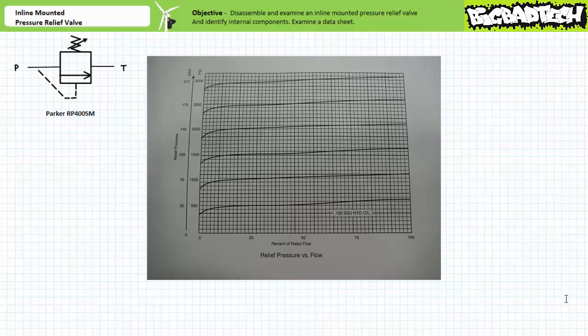The amount of diverted flow steadily increases as pressure approaches the full open value. This is to suggest that an actuator operating at regions near the set limit might show a lag in speed since an increasing portion of flow rate is being diverted through the progressively increasingly open pressure relief valve. This being said, you only experience this at regions very close to the set limit when an actuator is just about to stall out at the limits of travel anyways. Adjusting the pressure relief valve set value up or down, one would have to use an approximation of these curves to determine the behavior at other settings.